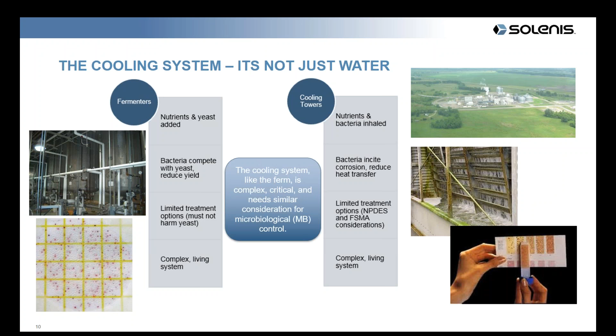So we wanted to talk about biofilms in general as a problem associated with your cooling tower that nobody really thinks about. We're all familiar with water treatment in terms of scale and corrosion, but as water treaters, we like to talk about the cooling water triangle. It's really a combination of good corrosion control, good deposit control, and good biological control. All three are interrelated. If you lose control of any of the three, you're going to have problems in the other areas.